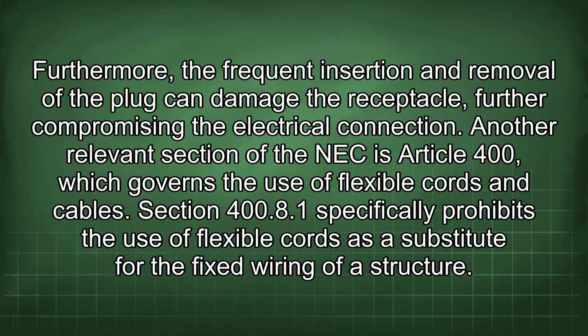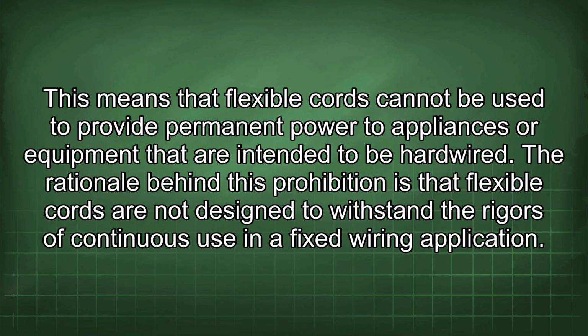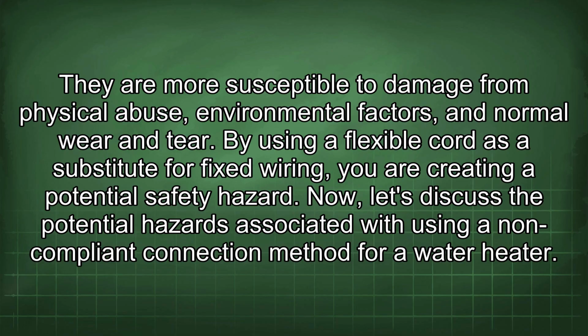Another relevant section of the NEC is Article 400, which governs the use of flexible cords and cables. Section 400.8 specifically prohibits the use of flexible cords as a substitute for the fixed wiring of a structure. This means that flexible cords cannot be used to provide permanent power to appliances or equipment that are intended to be hardwired. The rationale behind this prohibition is that flexible cords are not designed to withstand the rigors of continuous use in a fixed wiring application. They are more susceptible to damage from physical abuse, environmental factors, and normal wear and tear. By using a flexible cord as a substitute for fixed wiring, you are creating a potential safety hazard.